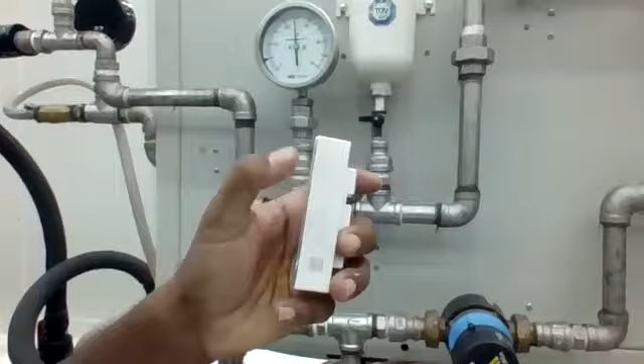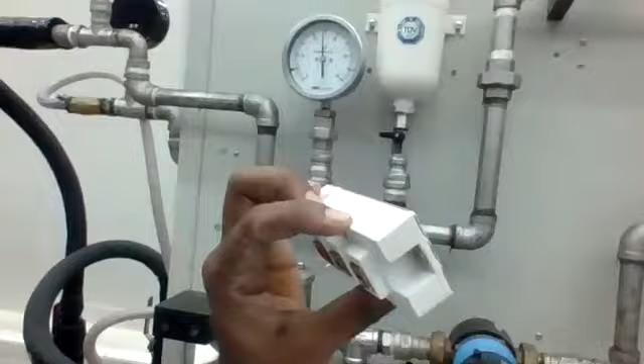One switch on top, one switch at the bottom, so one leg is this much. This leg is capable of withstanding around 32 ampere. So this is the capacity of one IGBT leg. A complete inverter, or the complete drive, has six diodes and six IGBTs. The complete drive, without the DC capacitance, will be tested in this particular setup.